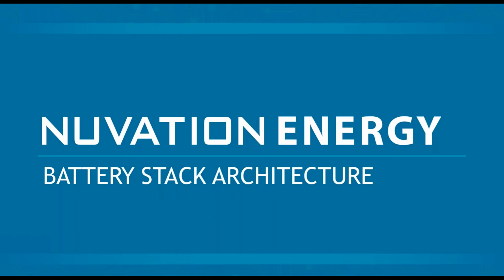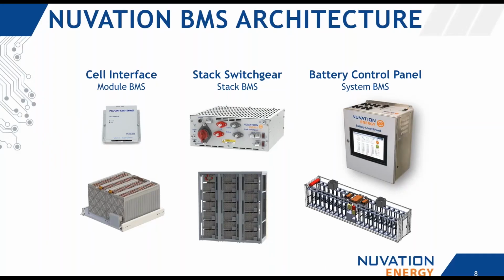With that introduction of who we are, I'm going to go into battery stack architectures and lay the groundwork for definitions that we'll be using throughout the webinar today. To start things off, this is our product lineup for protecting these cells throughout various stages. We've got the cell interface module, at the module level. It passes specific information to the stack switchgear, as well as performing the cell balancing routines. The stack switchgear, which goes in a rack, will handle the high current electrical connection between the stack and the outside system, whether that's a shared DC bus or the inverter or any other system that needs to make use of the battery. That's also where stack level fusing and contactors are located.